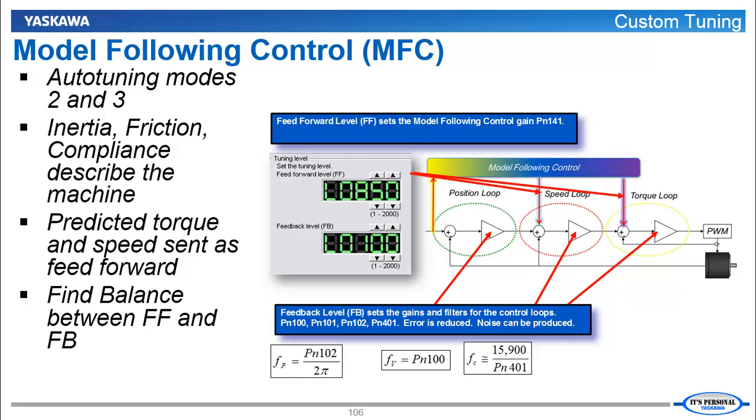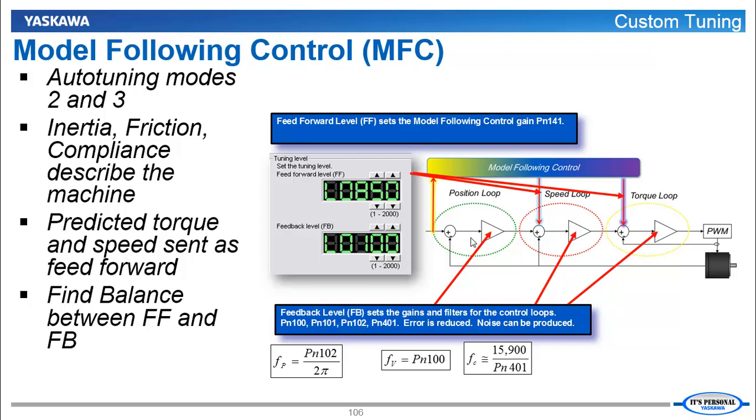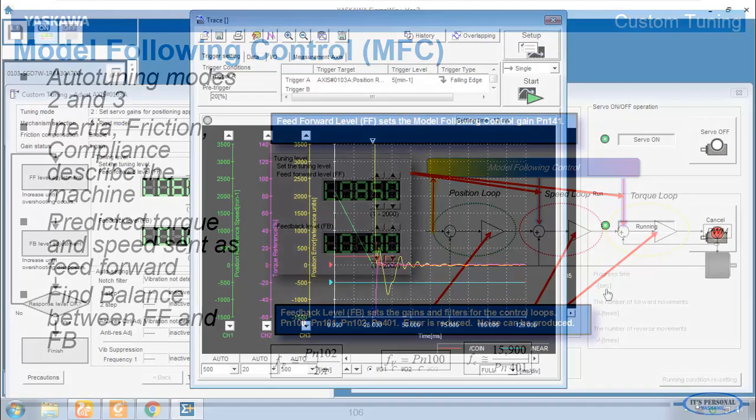If this model is accurate, then there will be very little position error and speed error in these loops. And the gains in these loops can be raised and lowered by this feedback level, proportionally to their bandwidth separation, in order to reduce any error between the predicted speed and torque of the model and the actual speed and torque required for the real machine. We're graphing the position error of the position loop right here. So to reduce this error, we'll need to increase the position loop gain. But of course, we need to also increase speed loop and torque loop bandwidth at the same time. And that's why it makes sense to do this using the feedback level.